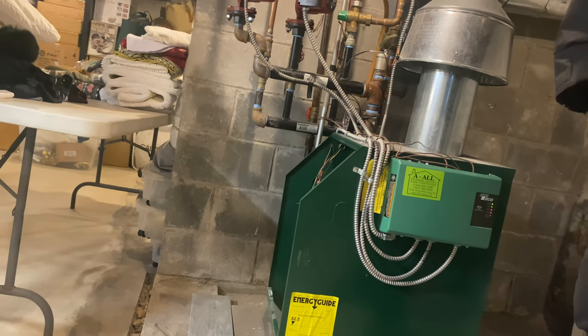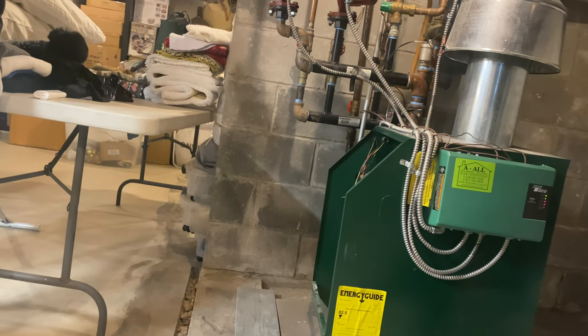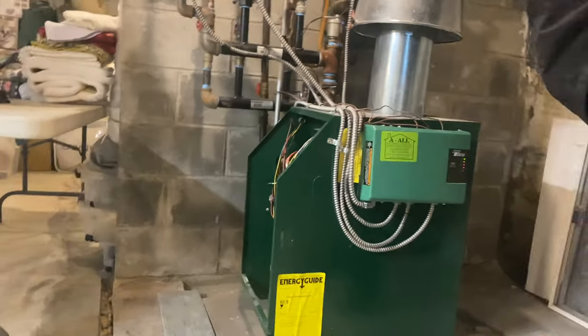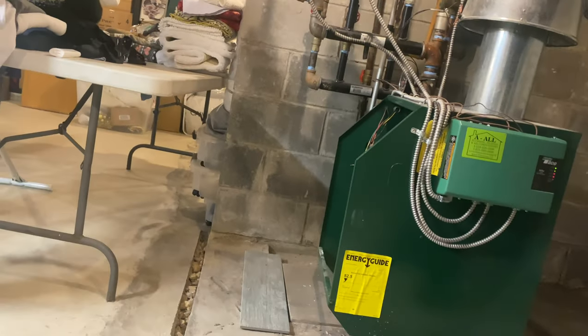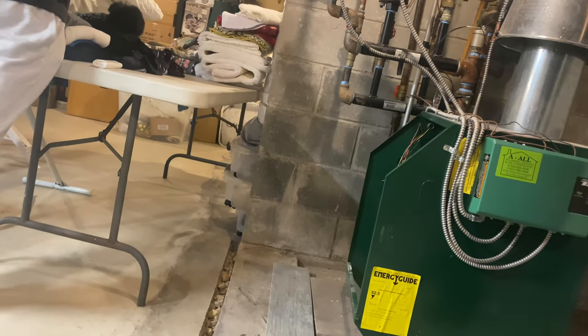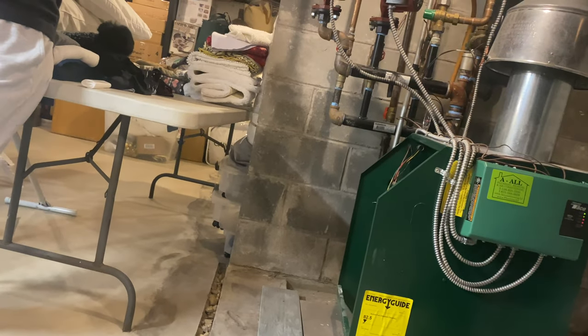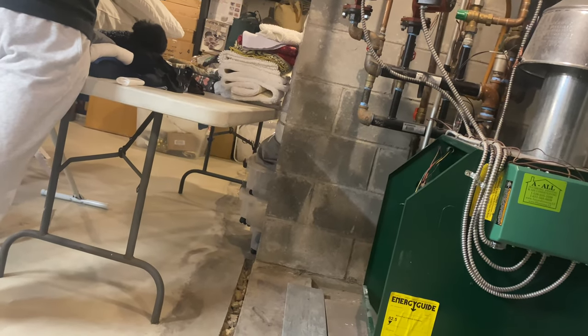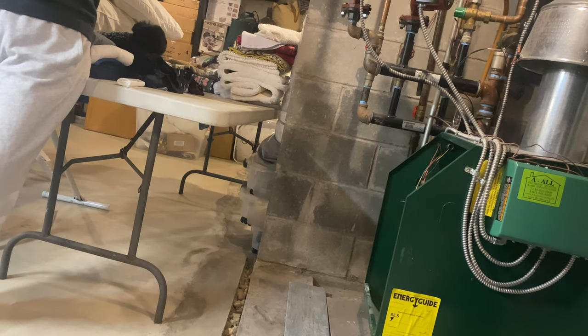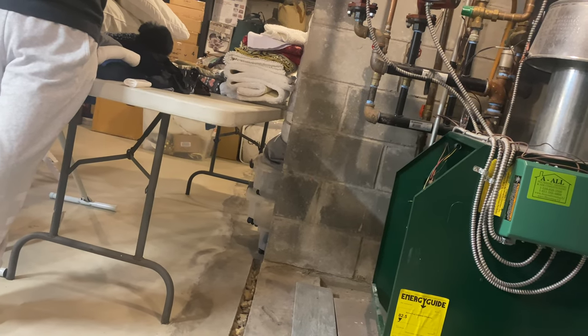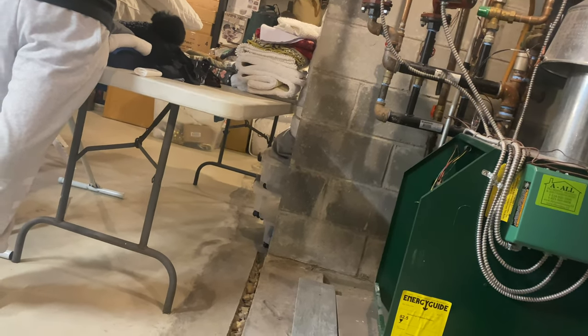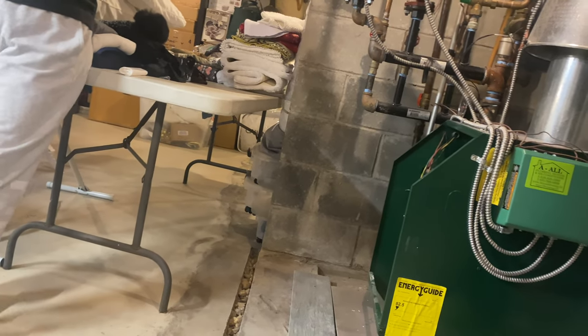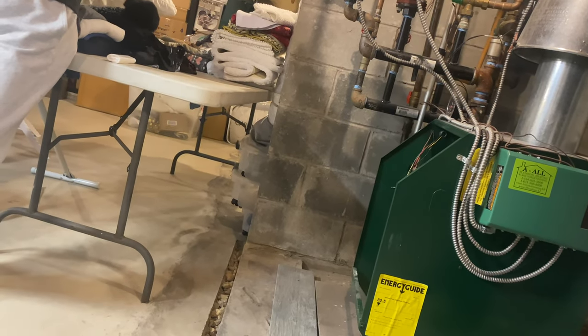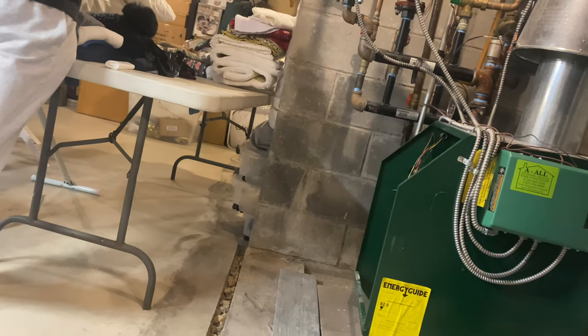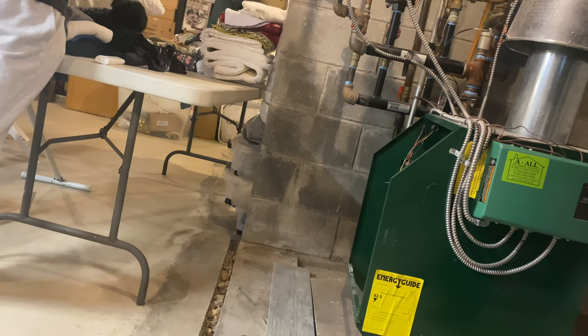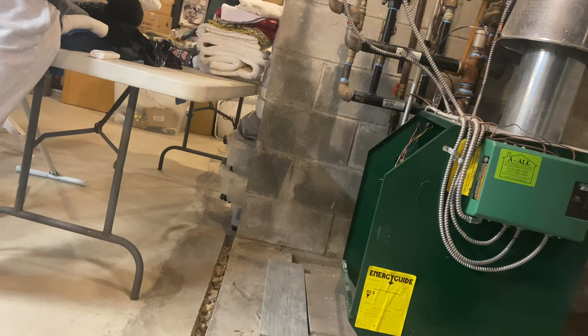So let's say, bear with me, this room requires a calculation which isn't normally done. Let's say the room requires 5,000 BTUs to heat it properly to design specifications, meaning proper insulation, proper windows, and direction like north plays a factor too. But the room only has, say, 2,000 BTUs of heating output. You have a loss of 3,000. The room will never be warm enough.